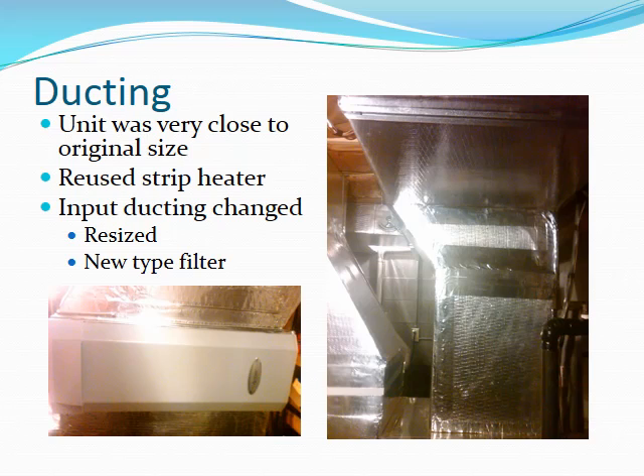Reconnecting the system was not a problem either. The unit was very close to the original size, and as I said, I reused the strip heater, so the entire top part of the duct stayed the same. The input ducting changed pretty dramatically. I installed a new type of filter, and the filter input was a lot different in terms of size and capacity, so I installed a high capacity, high efficiency filter. It was, I think, a little bit better than just a single monthly change filter that was originally provided with the system.